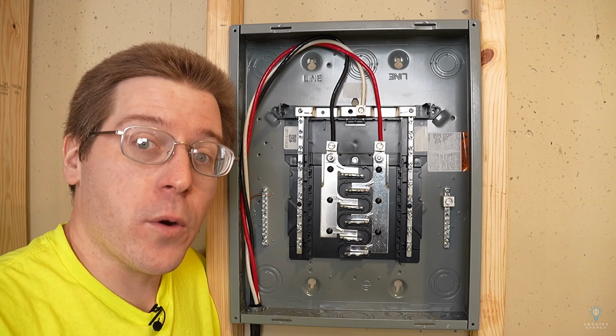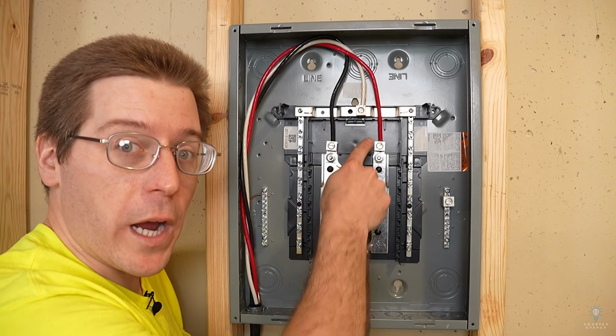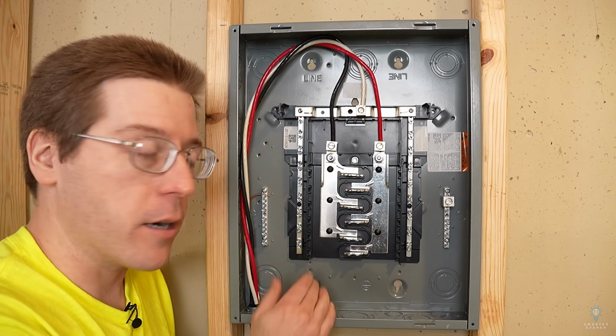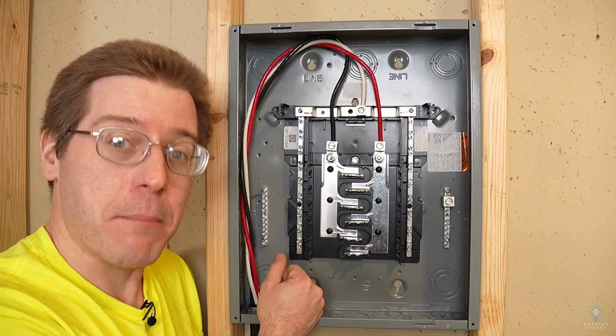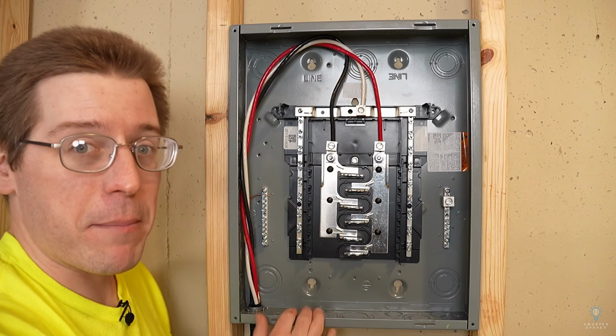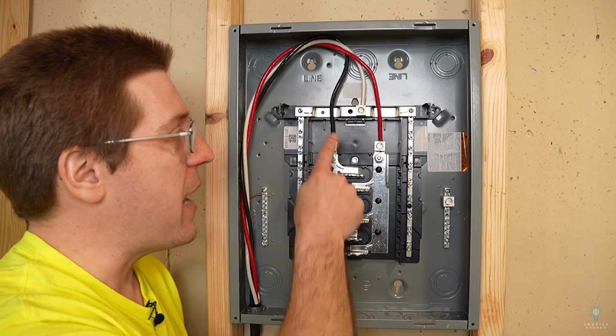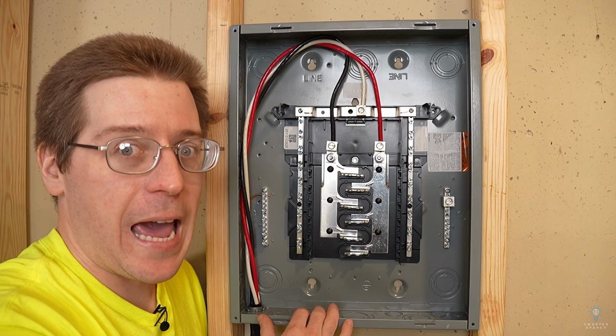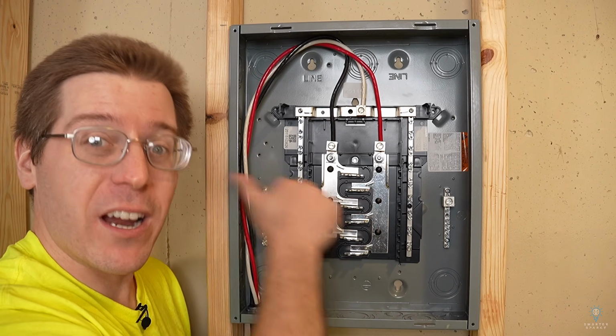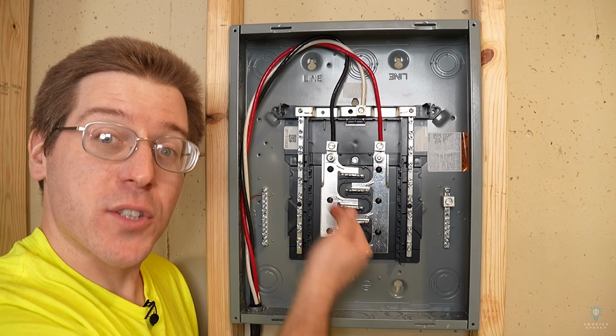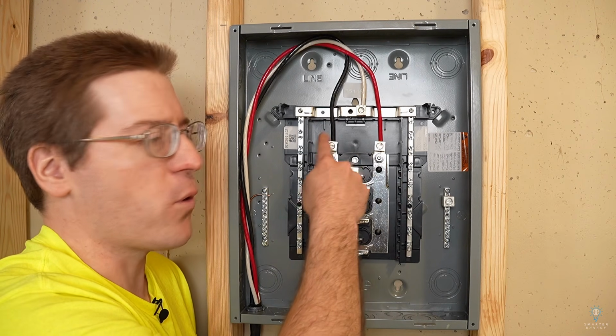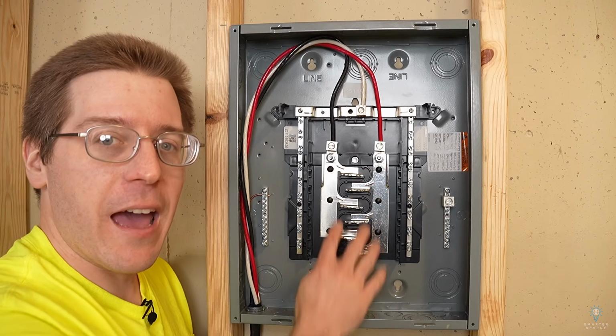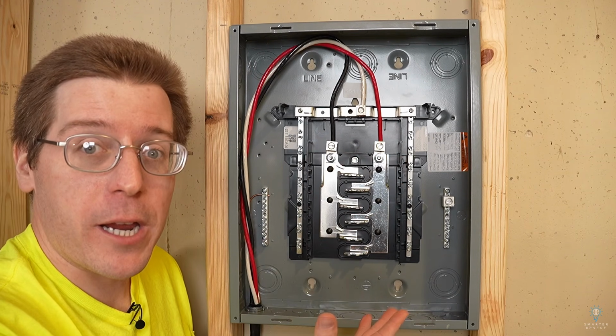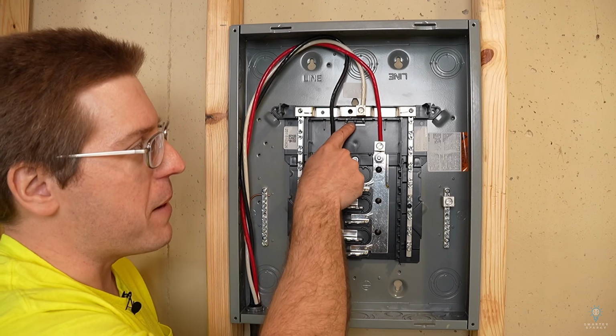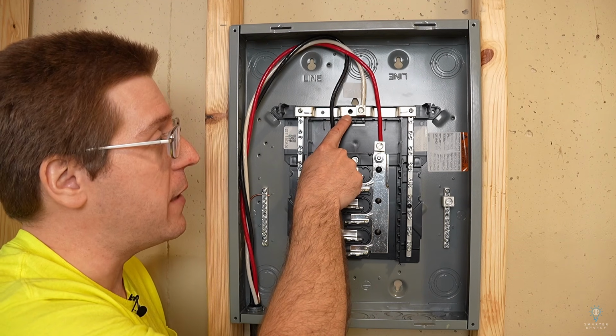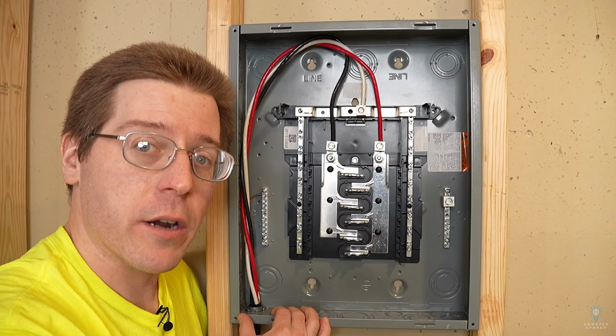That is acceptable. Another way to do it is you could land these wires right on the, let's say, 100 amp main breaker. So if this panel did have a 100 amp main breaker in it, you could land these wires right on that main breaker and feed the panel that way. That 100 amp breaker is going to do nothing more than act as a switch, because we're still going to have to protect this wire at 60 amps back at the main panel. So that 60 amp breaker in the main panel would trip before this 100 amp hypothetical breaker ever tripped. So yeah, if you did have a main breaker panel, you could still make it a sub panel. Just make sure you don't have that green bonding screw in there. And yeah, you could just run it on the lugs of your 100 amp main breaker.